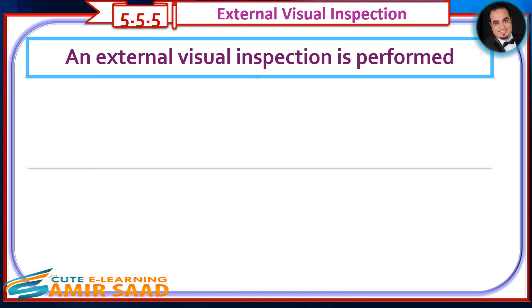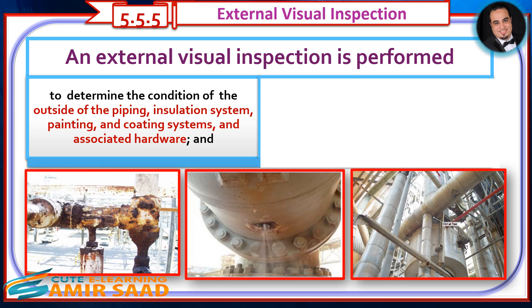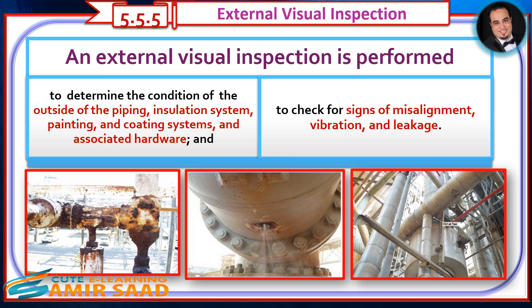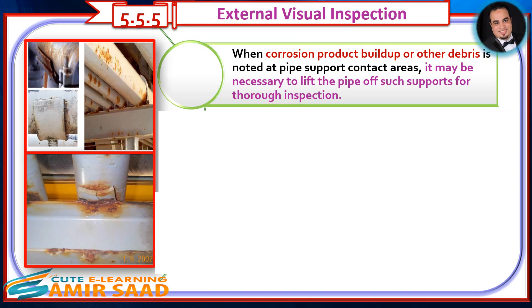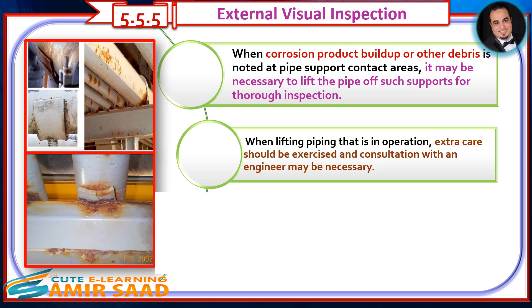An external visual inspection is performed to determine the condition of the outside of the piping, insulation system, painting and coating systems, and associated hardware, and to check for signs of misalignment, vibration, and leakage. When corrosion product buildup or other debris is noted at pipe support contact areas, it may be necessary to lift the pipe off such supports for thorough inspection. When lifting piping that is in operation, extra care should be exercised and consultation with an engineer may be necessary.